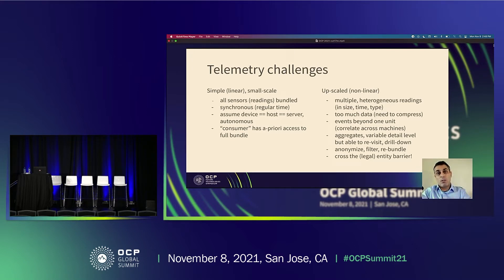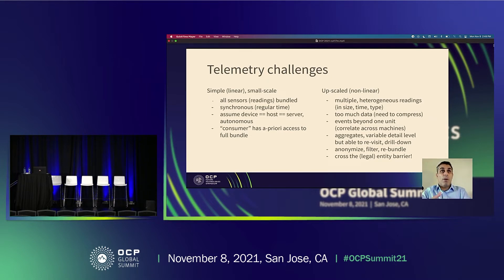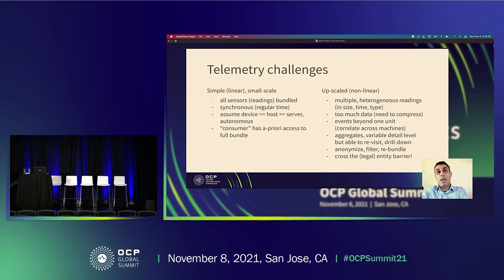Because we're concerned with a large number of interconnected units, we need to store and mark events across these units in a way that makes sense. For example, a power outage at a rack strip has affected many servers, and the rack power collection is not the same as the individual sensors on the server. We also want to see anomalies in this ocean of data, starting with an aggregate to spot possible anomalies and then drill down to find individual measurements that contributed to what the anomaly may be.